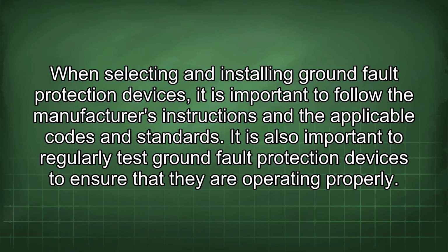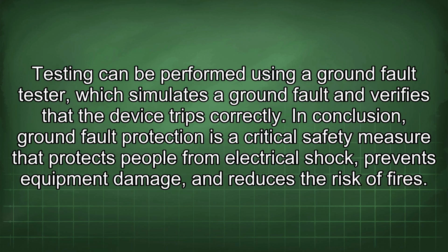It is also important to regularly test ground fault protection devices to ensure that they are operating properly. Testing can be performed using a ground fault tester, which simulates a ground fault and verifies that the device trips correctly. In conclusion, ground fault protection is a critical safety measure that protects people from electrical shock, prevents equipment damage, and reduces the risk of fires.